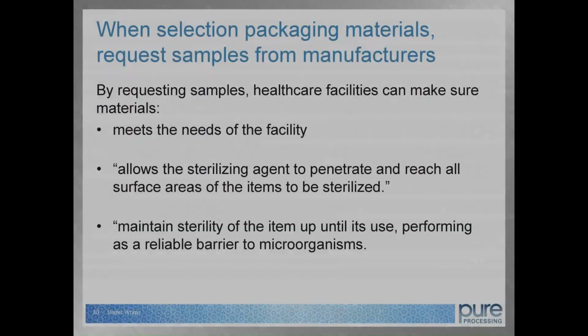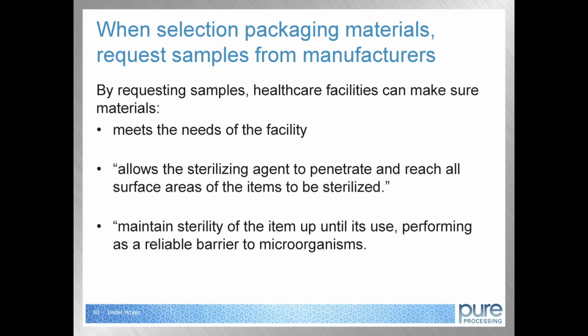The Association of Surgical Technologists Standards of Practice for Packaging Material and Preparing Items for Sterilization recommends requesting samples of sterile packaging materials from manufacturers prior to adoption and purchase of material. By requesting samples, healthcare facilities can test materials to ensure that the wrap meets the needs of the facility and allows the sterilizing agent to penetrate and reach all surface areas of the items to be sterilized. By testing wrap materials, facilities can check to see if the material maintains sterility of the item up until its use, performing as a reliable barrier to microorganisms.